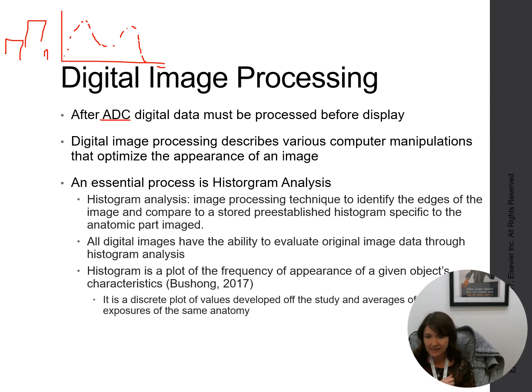At this point, after it gets to the raw data histogram, it's really going to start going through those pre-processes. The first thing it's going to do is apply the field of view recognition. Basically, it's going to say, okay, you selected a hand on my workstation. A field of view for a hand usually starts at this brightness level and ends at this brightness level. And that's going to be therefore my S-min and my S-max. And halfway between the two is my S-average.